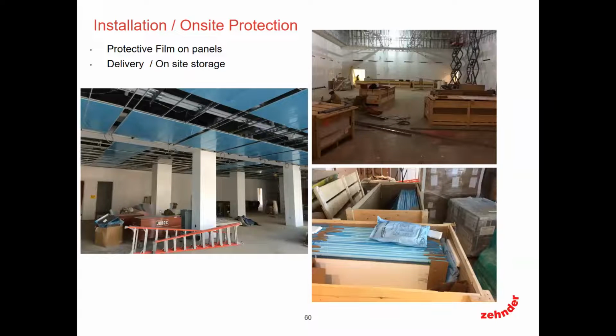As far as on-site protection, things to be aware of: all the panels from all manufacturers will ship with some sort of film on them and protective gear, just because it is a finished product going in the ceiling. The other thing I'll also recommend in your specifications is some sort of crates or protection, especially if they're not going to be installed immediately. Over the years, I've experienced that these crates or boxes, depending on how they ship, become workbenches or ladders for other trades going through. So if you could protect those panels, I definitely recommend it's worth the money.